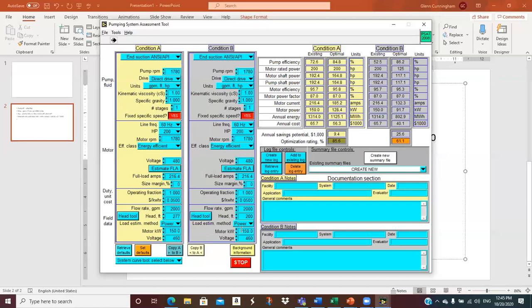75% pump efficiency. Okay? So then I come in here and I look at this. Well, that's not 75%. Well, so how can I make that get bigger? Well, I can reduce the power. I can guess the power until I make the efficiency 75%. So, I don't know, let's just put 100 in there. Well, 78, not quite that good. Whoops, 100 point. That's pretty close.